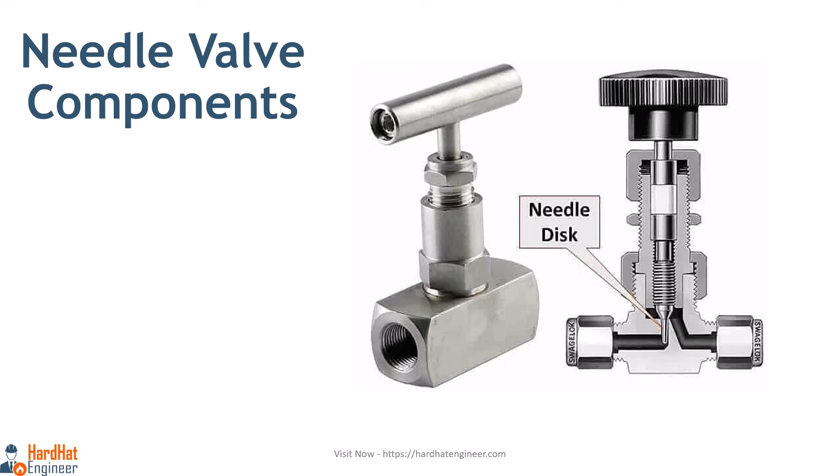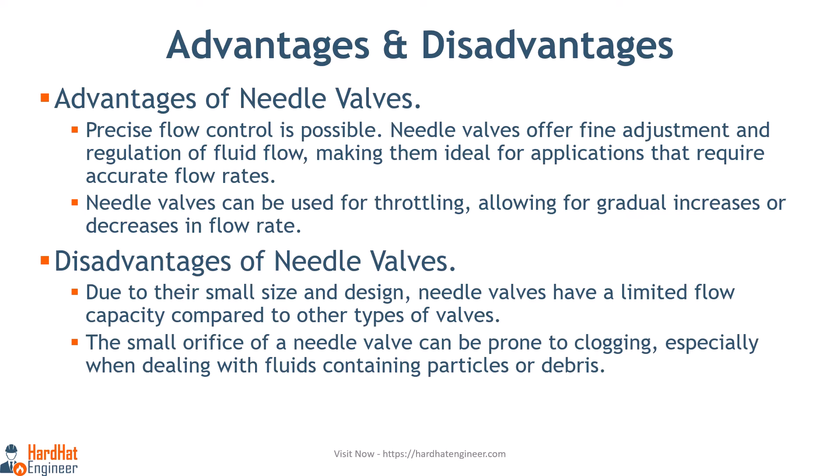Needle valves can be used in situations where flow must stop gradually, and in applications where precise adjustments of flow are required or where a small flow rate is desired, such as sample points in piping. Advantages: precise flow control is possible; needle valves offer fine adjustment and regulation, making them ideal for accurate flow rates, and can be used for throttling. Disadvantages: limited flow capacity compared to other valve types, and the small orifice can be prone to clogging when dealing with fluids containing particles or debris.